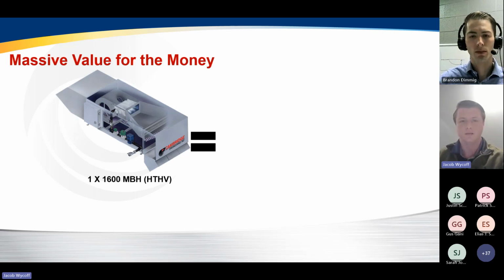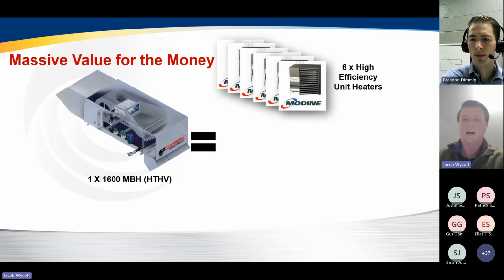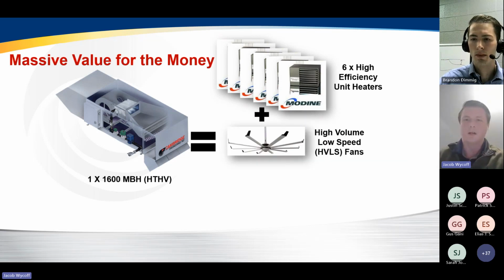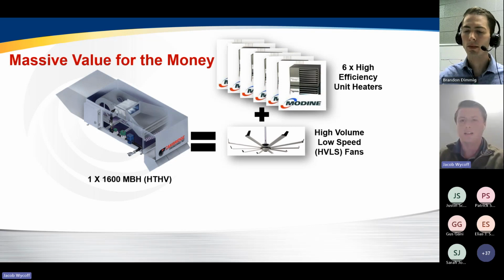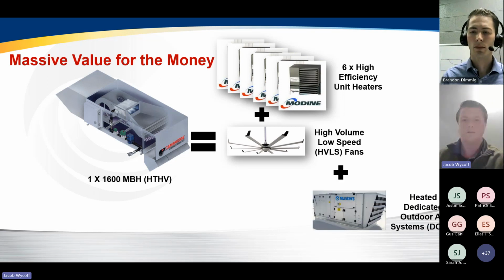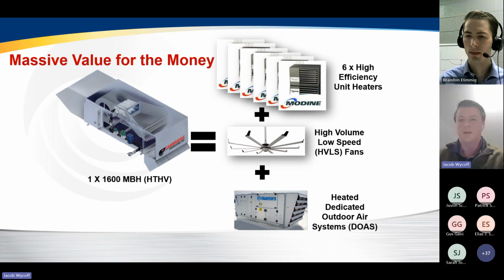So you get the very efficient units that are going to last for a long time, that are going to be very simple and require very little maintenance. But you're also eliminating many pieces of equipment to get the same effect. So with one 1600 MBH HTHV unit heater, you're able to eliminate 6 high efficiency 300 MBH unit heaters. You're no longer going to require some kind of auxiliary destratification technology like HVLS fans. And you're no longer going to require some kind of heated DOAS system to be able to provide that fresh outside air.